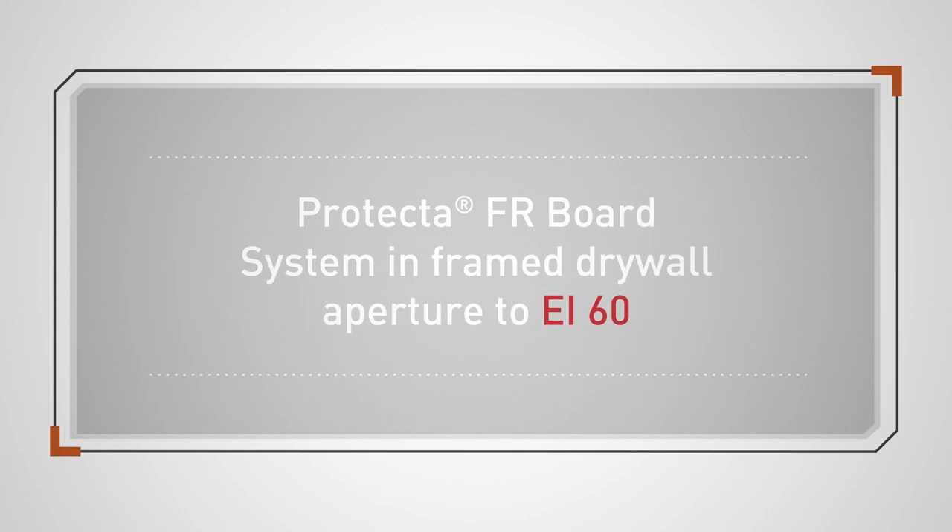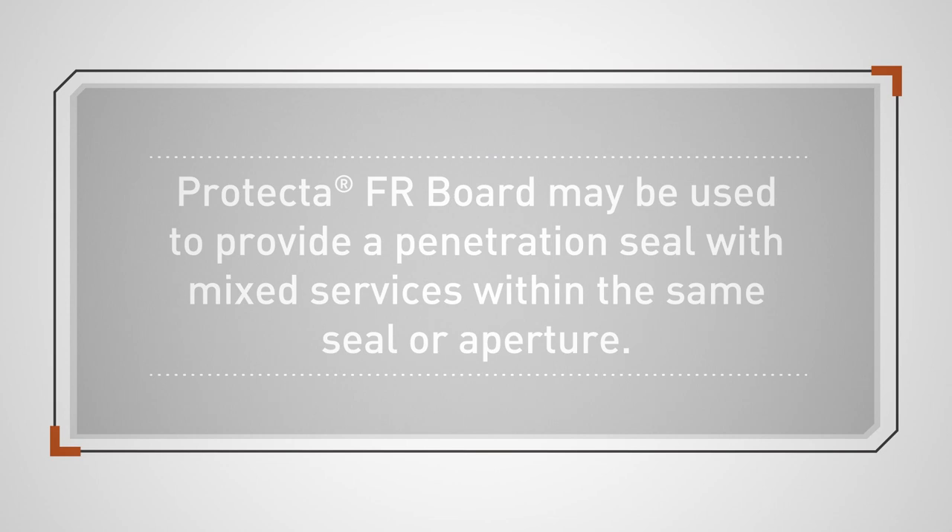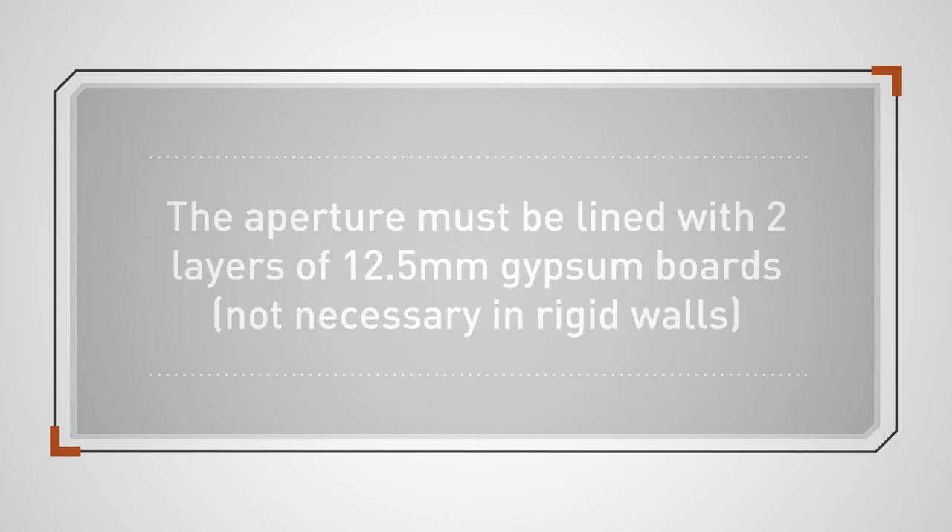Protecta FR Board System in Frame Drywall Aperture to EI60. Protecta FR Board may be used to provide a penetration seal with mixed services within the same seal or aperture. The aperture must be lined with two layers of 12.5mm gypsum boards, which is not necessary in rigid walls.